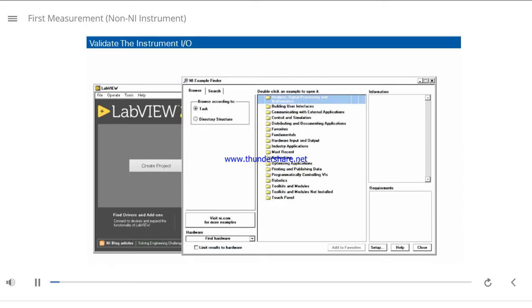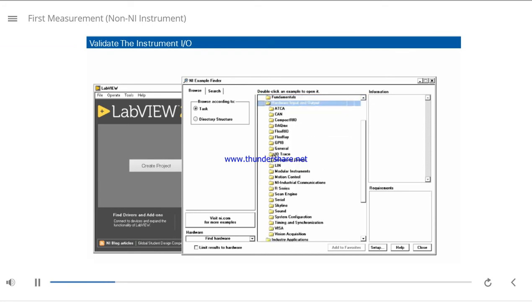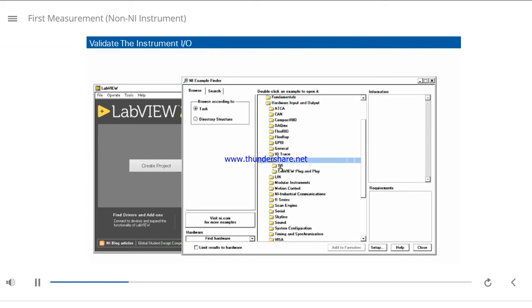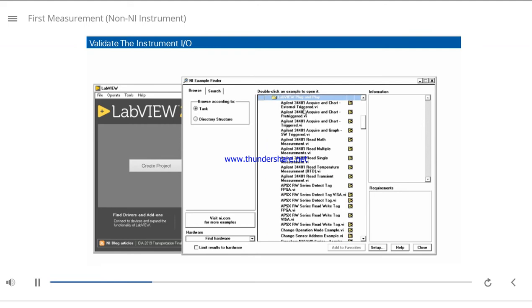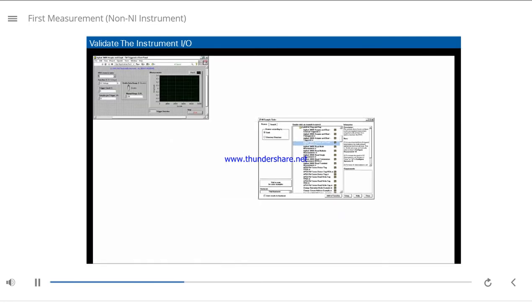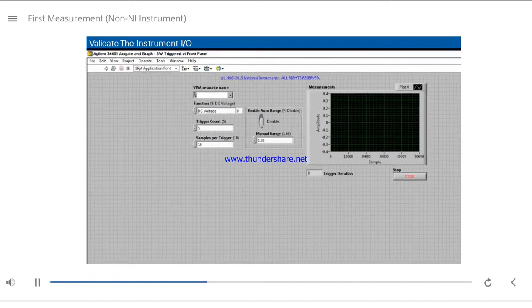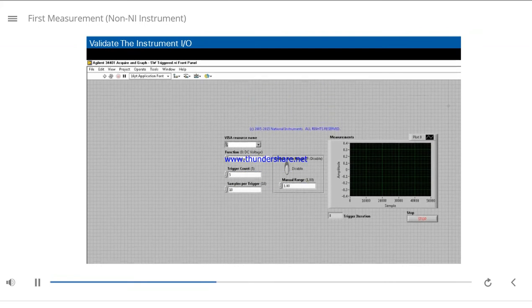After configuring your instrument in NI-MAX and installing an instrument driver, find its example programs in Help > Find Examples, on the Browse tab under Hardware Input and Output. Navigate to Instrument Drivers, then LabVIEW Plug and Play, and now we see our specific instrument's examples here. Select the example program closest to what you want to do, and run it to validate that the instrument is returning the expected results.